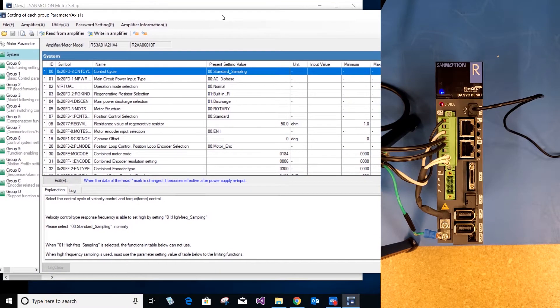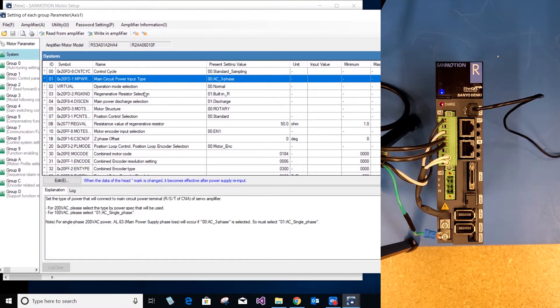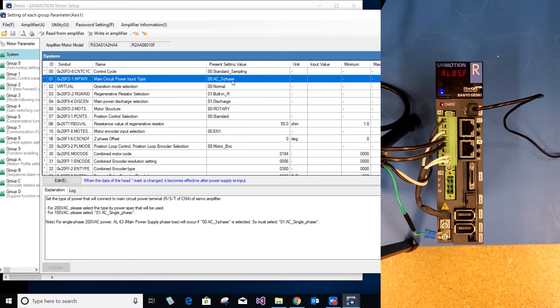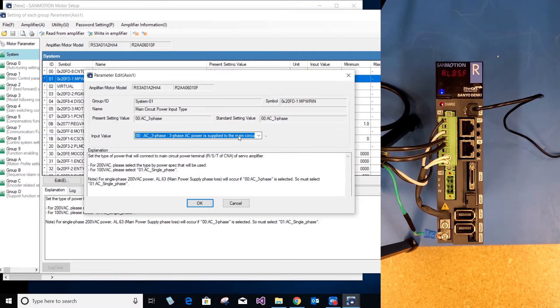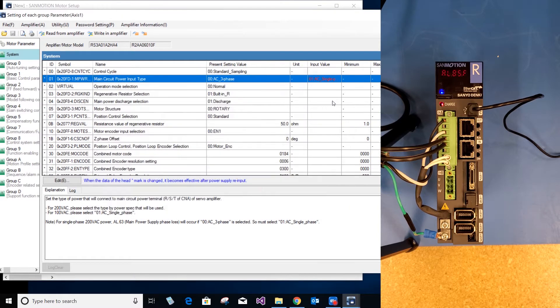First one would be main circuit power input type. Default is three phase; I am using single phase, so I will change that parameter. If you are using three phase, you do not need to change this parameter.